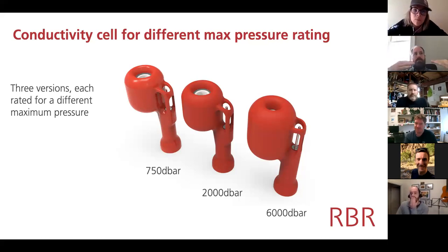And that is that that's only good if you're in still water that doesn't have a lot of bubbles entrained into it. Once you have bubbles entrained into it, every conductivity cell in the world is doing a volume averaged measurement. And that volume averaged measurement sees bubbles as perfect insulators. So if you've got 50% bubble and 50% water, your conductivity reading is off by 50%, and there's nothing you can do about it. So you certainly don't want those bubbles to adhere and stay there. Fortunately, most profiling instruments go down, and those bubbles just disappear, and then the gas dissolves into solution. So in still water conditions where there are not large bubbles, you can get accurate measurements to kind of the 10, 15 centimeter level.